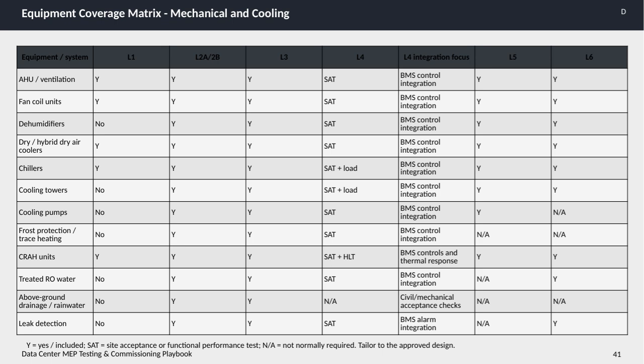For instance, air handling units and fan coil units are included in almost all levels, right from L1 up through L6, with an emphasis on site acceptance testing at L4 and BMS control integration to ensure proper building management system operations. Dehumidifiers and cooling pumps, on the other hand, start from L2A/2B, indicating they aren't involved in the earliest testing phases, while frost protection and treated RO water systems come in later and sometimes are not required at certain levels, depending on the design. Cooling towers and chillers are critical too, with testing including both site acceptance and load testing by L4, reflecting their importance in maintaining cooling capacity.